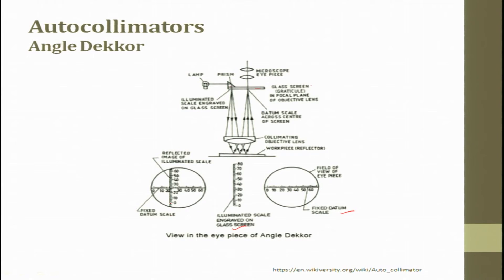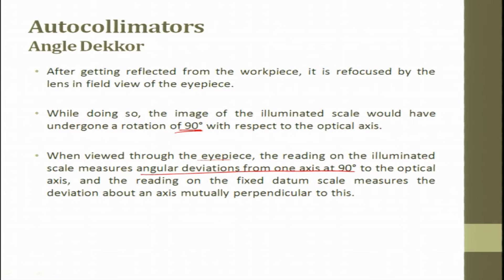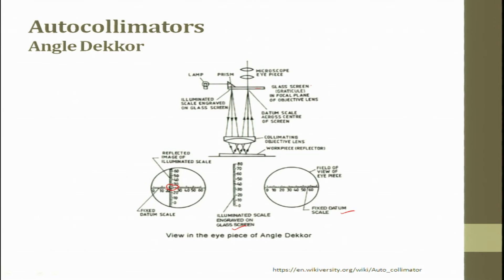You can see here — this is 0 and somewhere here is the measured reading. In the angle Dekkor, a prism is used with a collimating objective that hits a flat surface; reflection happens, and there is a screen with an engraving. The reflected data goes there, the screen has its own fixed datum, and the deviation between these two is measured through the eyepiece. The angle Dekkor is a special kind of autocollimator and is also used for angular measurement.